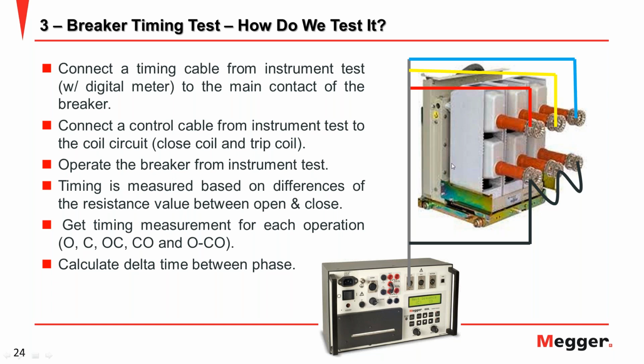After you connect to the main contacts, you need to make the connection to the control circuit, to the coil, to trigger the breaker to operate. Then you do open, close, and close-open operations. You get the timing, and you can calculate the delta time between phases. I believe all equipment testers for this purpose will provide you the delta or difference time between the three phases, because the main goal is we want to know the difference between all three phases.